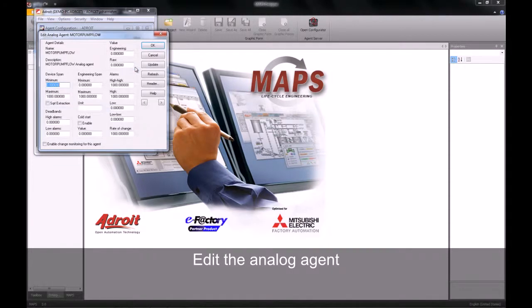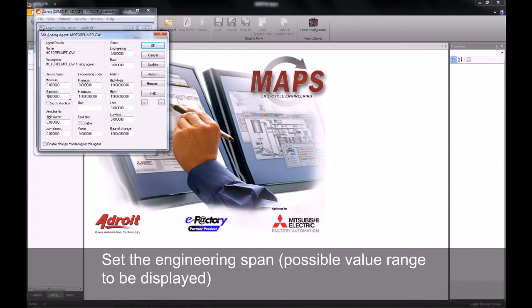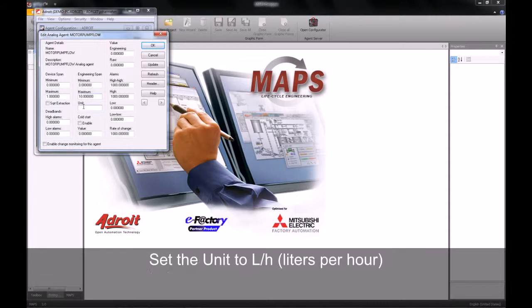We will then go along and select the edit button to edit our agent. We will be adjusting the device span of our analog agent — this is the span in the PLC. We can then specify an engineering span or range, which will be what we display to our operator. We're also going to give our analog agent a unit value, which will be liters per hour.